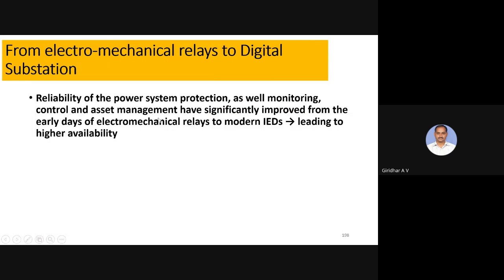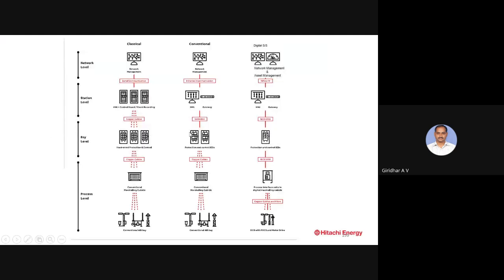So from electromechanical relays to digital. If you could see the different classical, conventional and digital substations, there are different changes and different layers you can see. Classical serial communications were there with a faster rate, then Ethernet communications. Still in the digital, nowadays, the process bus with the IEC 61850 standard they are using, through the process bus. So in that way, very fast actions they are taking.